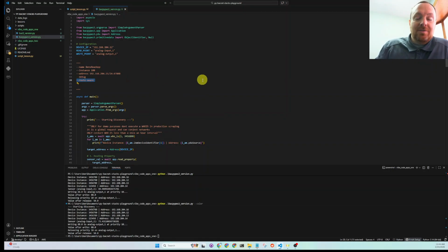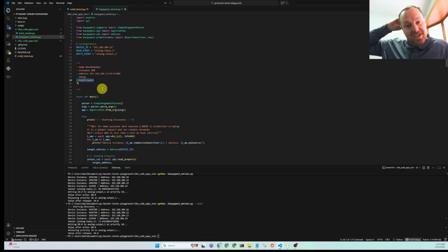I personally have never used this either, but I think this can come in handy: sometimes you get a contractor that'll set up a BACnet router between MSTP networks and IP networks with the same name and the same network number, and sometimes your application won't work.